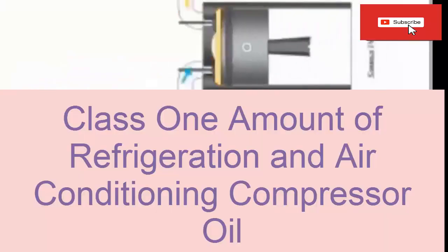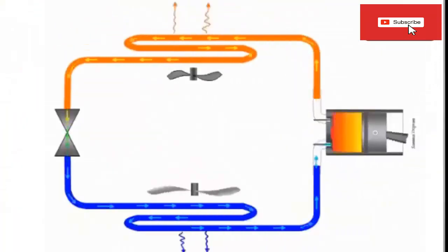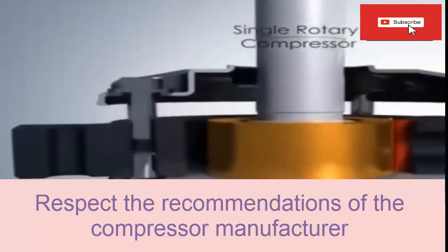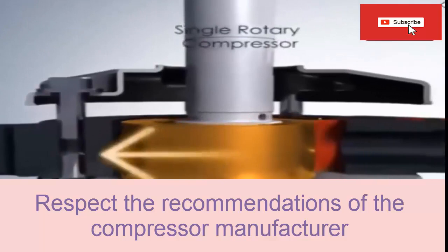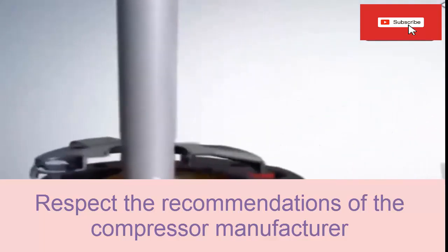Today we present the recommended amount of oil for refrigeration and air conditioning compressors. Let's start by saying that new compressors come from the factory with the amount and type of oil tested by the manufacturer for a certain gas or class of refrigerant, and these specifications must always be respected. But in some repairs it may be necessary to change the original lubricant, and the question may arise of how much oil the system requires.